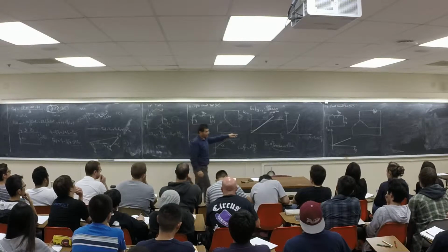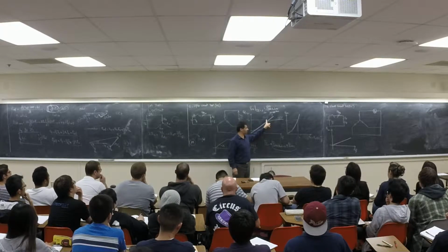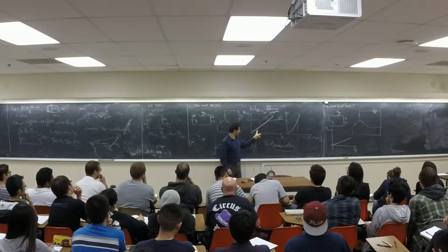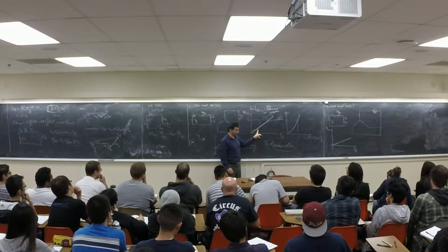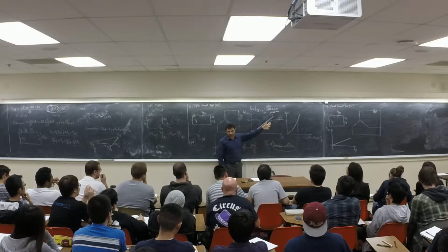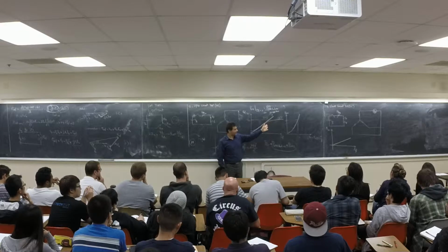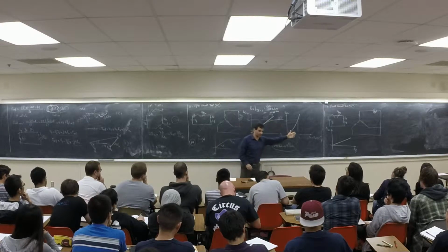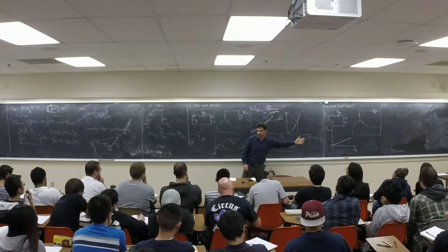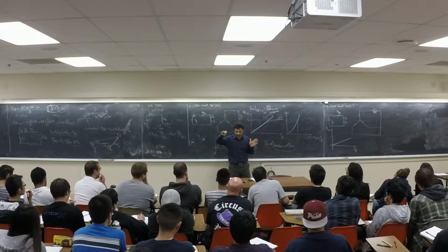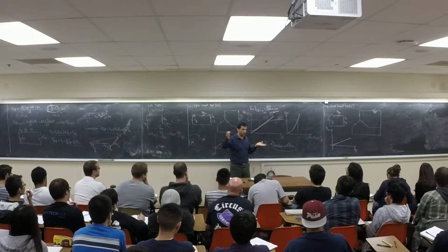See, the saturation happens somewhere, this is rated, right? It happens somewhere here, right? It's going to be maybe around here, not even past this point. Because if you go bigger than this one, it's going to kill the machine. The machine is shorted, right? Even if we have 30% of the rated voltage, it's going to be too much and will kill the machine. It's shorted, right? So basically, the voltage is going to be pretty linear, right? If the voltage is linear, short circuit current also will be linear.